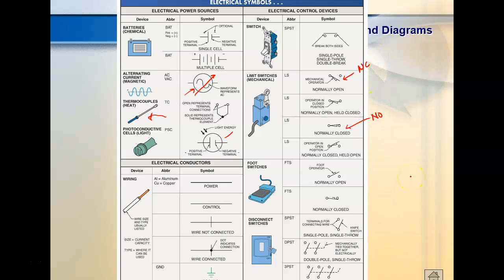Now, limit switches—when you park your device, sometimes the device, when it's at rest, is sitting on top of a limit switch. If it's a normally open limit switch and it's sitting on top of it, we'd use this symbol. What you can do with these is look and see what gravity's trying to do. So gravity's trying to open this one, so it's normally open, right?